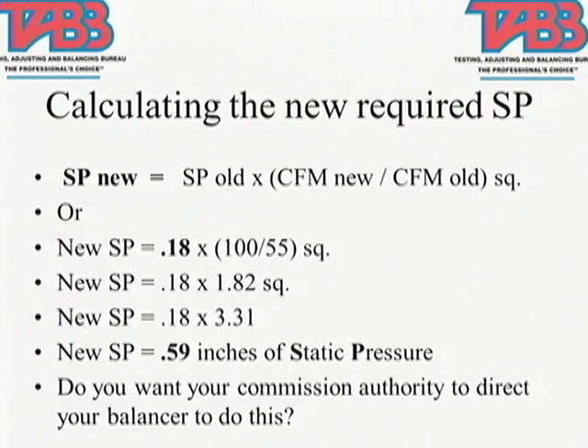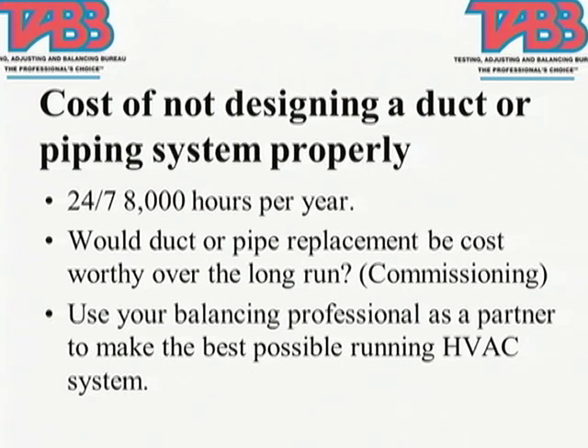Otherwise, we have these energy costs where we're ballooning it up, and then we start saying, well, we have duct leakage in there. We start getting into higher pressure classes of duct systems. Do you want your commissioning authority to direct your balancer to do that? The cost of not designing a system properly, of course, is 24/7, 8,000 hours per year. Would duct or pipe replacement costs be worthy in the long run? It's really up to the commissioning agent. Use a balancing professional or the balancing industry to make the best possible running HVAC system.